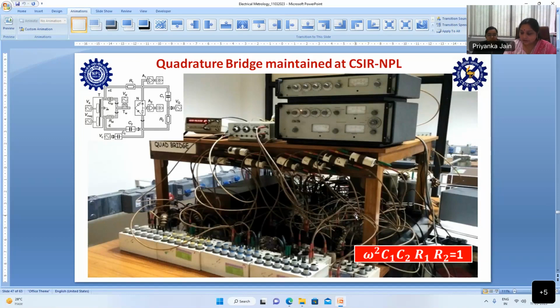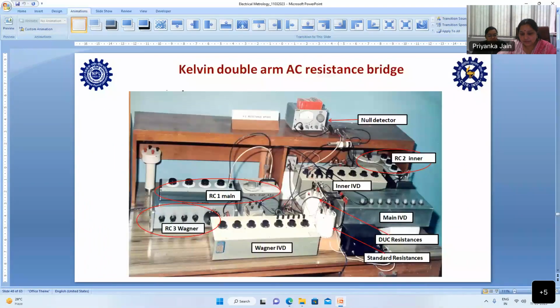Now we have the 1 kilo ohm resistance standard. From there, we are disseminating 1 ohm to 1 mega ohm through the Kelvin double arm AC resistance bridge. Customers' resistance standards are also calibrated through this bridge. You can see here the resistances which we are comparing. One is the standard and one is the DUT. Here you have to put the IVDs: one is the ratio arm, and one of the arms is formed by the resistances which are to be compared.